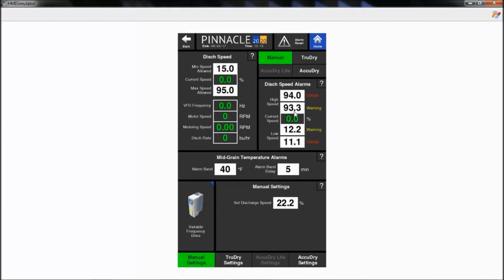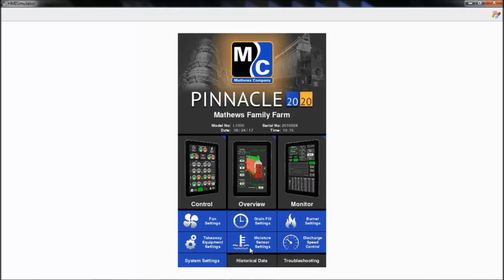An alarm setting is going to trigger an alarm but continue trying to operate the dryer. Right now the dryer is not running, so we're at 0. But if we were running at 22% like our set point is, and then we went up above 93.3%, we'd get a warning alarm, a yellow warning alarm. If we continued to increase speed up above 94.0%, we'd get a cooldown alarm, which would eventually shut us down. And on the low end, we have similar alarms. These alarms have to do with discharge, but they come into several places throughout the software.